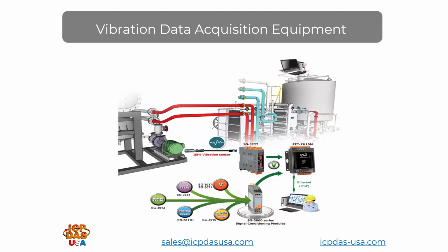And you can choose a number of different signal conditioning modules from the SG3000 series to measure input signals such as voltage, current, temperature, via thermocouples or RTDs, and provide 0 to 10 volts, 0 to 20 milliamps, 4 to 20 milliamp output signals. From the PET-7H16M over Ethernet, our data goes to a PC running a Viva Edge SCADA with control and monitoring screens.